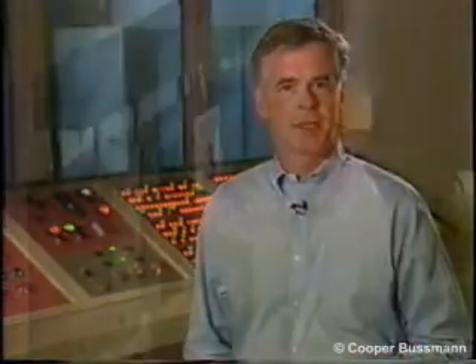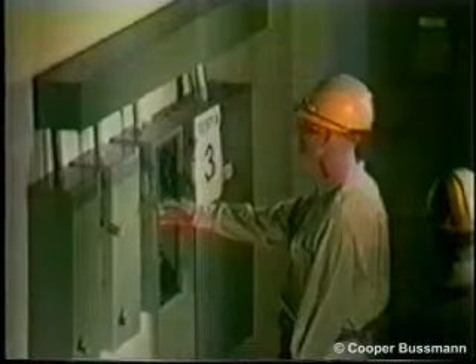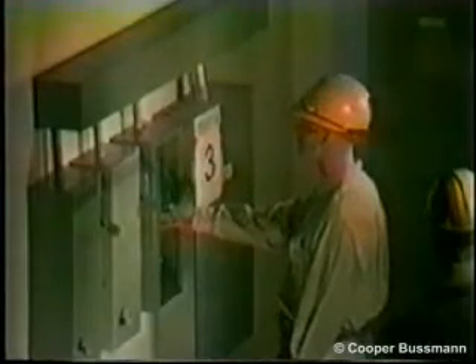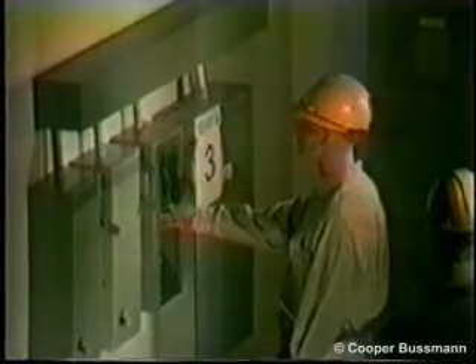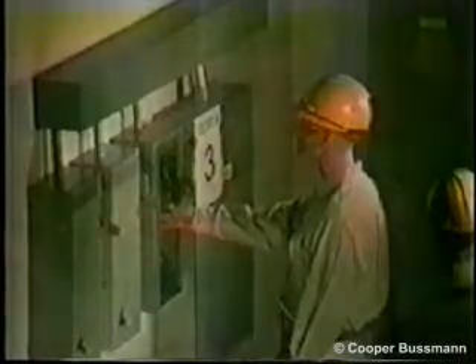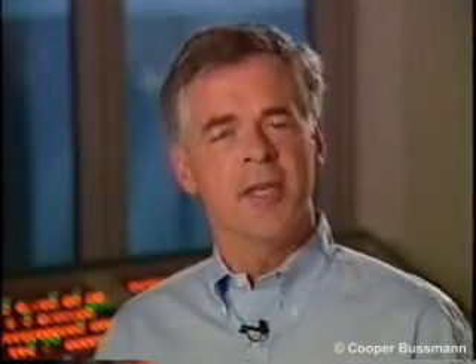To demonstrate the advantage of current limitation, the next test uses a 601 amp Class L current limiting fuse to protect the same circuit. Notice the dramatic reduction of arc energy and gases. This worker may get home yet tonight. Using current limiting circuit protection will significantly reduce the flash hazards that are associated with high energy arc flashes. An effective safety program pays dividends.